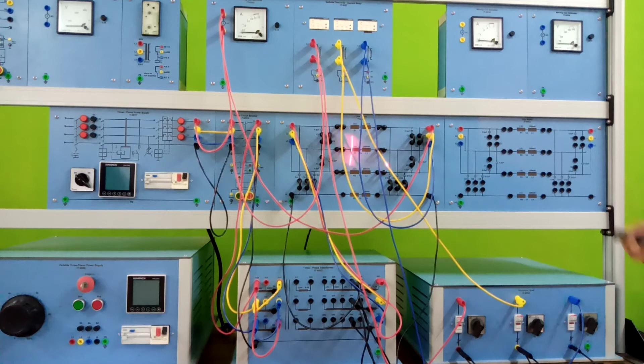Okay students, so now it's time to just have a look at the output terminals of the relay. Okay, so you can see there are 3 points. One is the normally closed, normally open, and then a common. So normally closed means that under normal conditions these two connections will be closed. So let's check. You see now the meter is beeping, it is closed. Okay, so now it's a normal condition. And normally open means that under normal operating conditions these two contacts will be open. See, so now no beep, it means that there is no contact between these two connections.